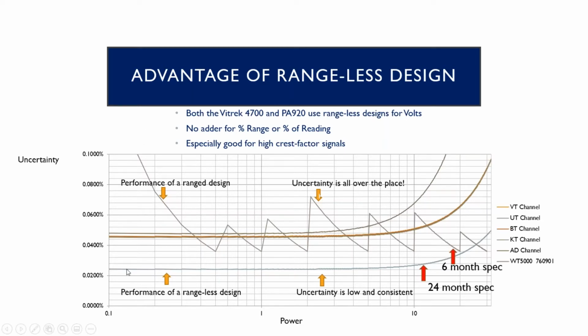One of the nice things about this is it's a lot easier to determine your uncertainty because they're not constantly changing and all over the place. Okay. So, by the way, another advantage of this is we're really good with high crest factor signals, because with other devices, if you've got a signal that varies from small to large, you would put it on a high range, and then it wouldn't be very good at measuring the low part of the signal. With ours, since there's only one range, really, it's rangeless. It doesn't really matter. It can see the small signal, it can see the large signal. It's accurate at both ends of the scale.